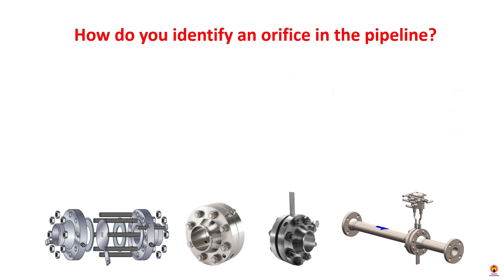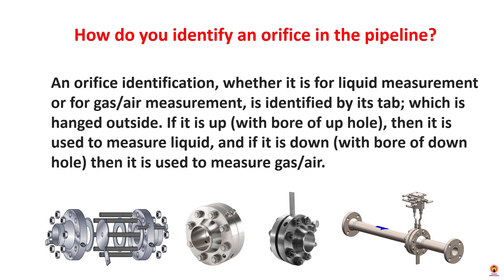How do you identify an orifice in the pipeline? An orifice identification — whether it is for liquid measurement or for gas and air measurement — is identified by its tab which hangs outside. If the bore hole is up, then it is used to measure liquid. If it is down, with the bore hole down, then it is used to measure gas or air.